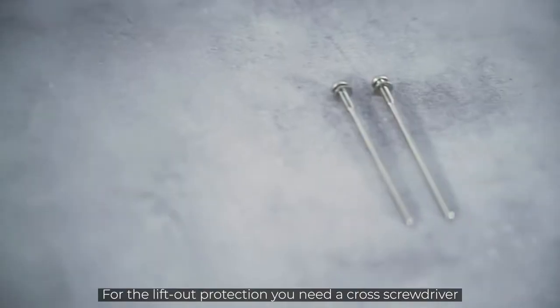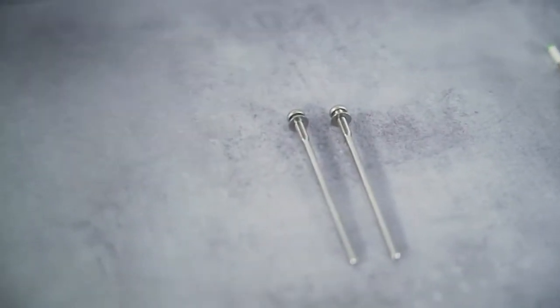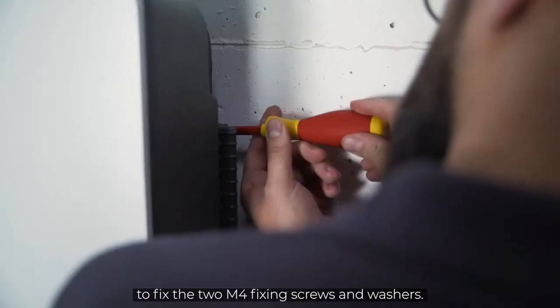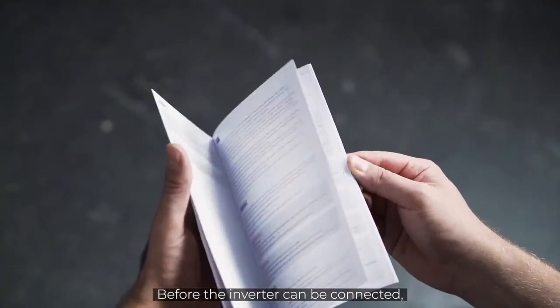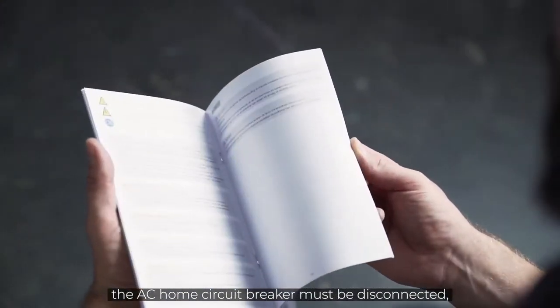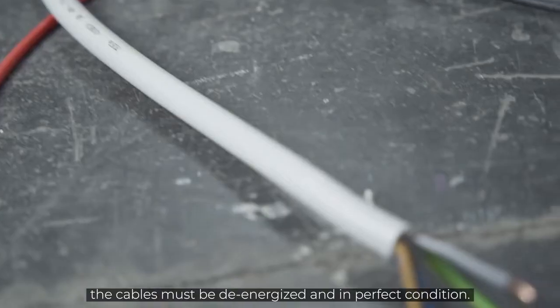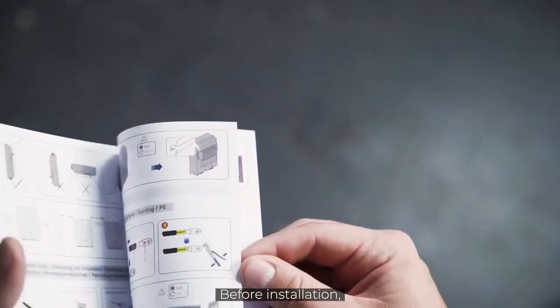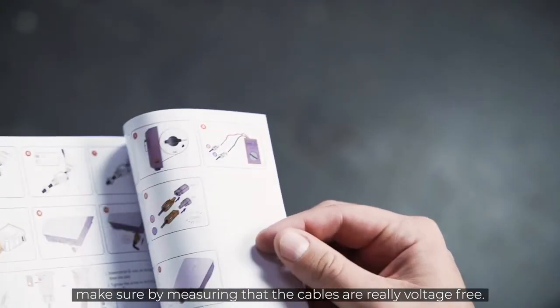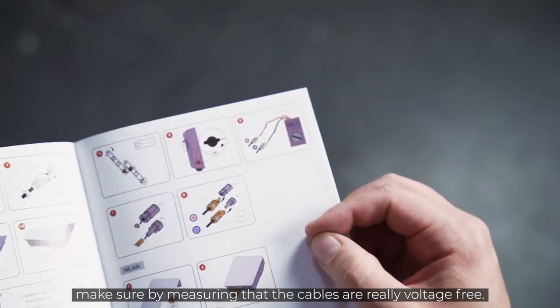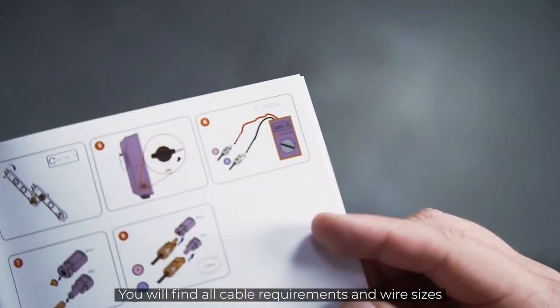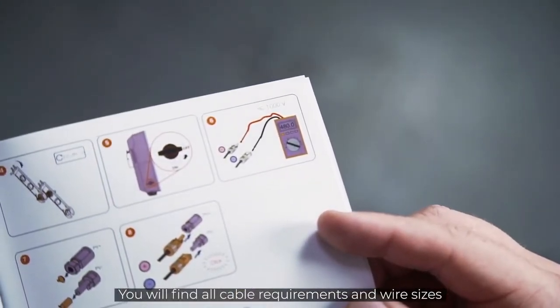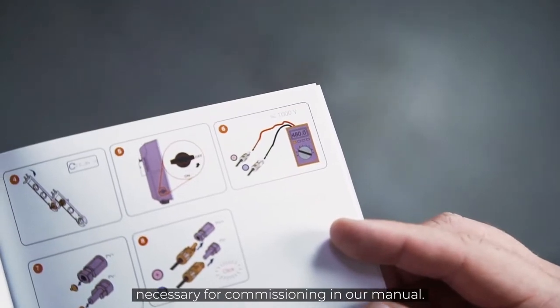For the lift-out protection, you need a cross-screw driver to fix the two M4 fixing screws and washers. Before the inverter can be connected, the AC home circuit breaker must be disconnected, the cables must be de-energized and in perfect condition. Before installation, make sure by measuring that the cables are really voltage-free. You will find all cable requirements and wire sizes necessary for commissioning in our manual.